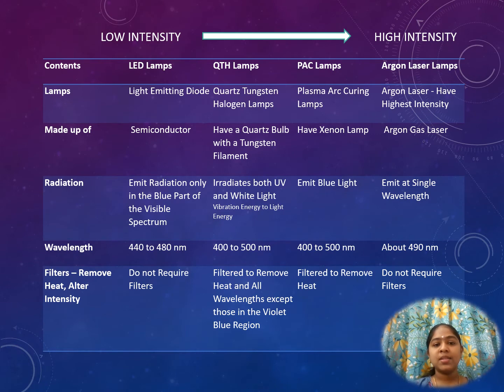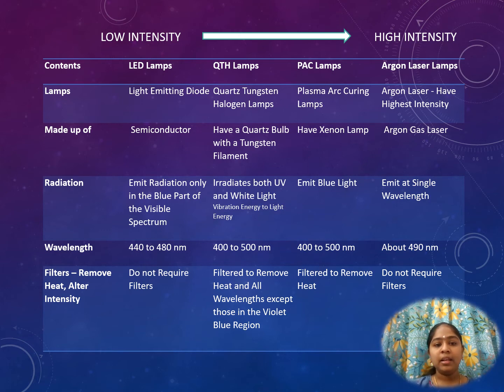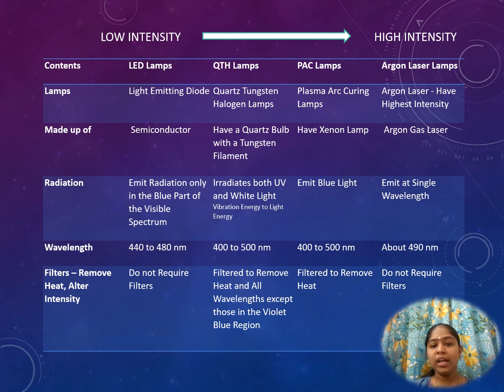Comparing the curing lamps — LED, QTH, PAC, and argon laser — LED lamps have the lowest intensity while argon laser lamps have the highest intensity, in order from low to high intensity. LED lamps contain a light emitting diode; QTH is a quartz tungsten halogen lamp; PAC is a plasma arc curing lamp; and argon laser lamps have the highest intensity. LEDs are made up of semiconductors, QTH is made up of a quartz bulb with a tungsten filament, PAC lamps are made up of a xenon gas plasma, and argon laser lamps use argon gas laser.